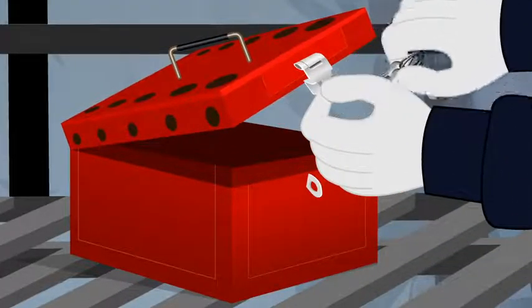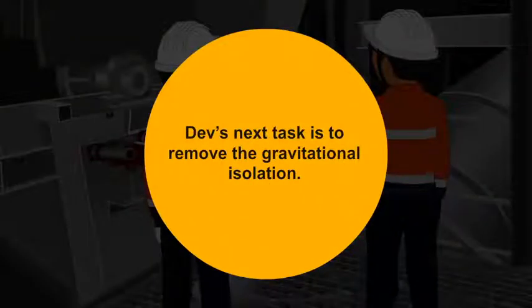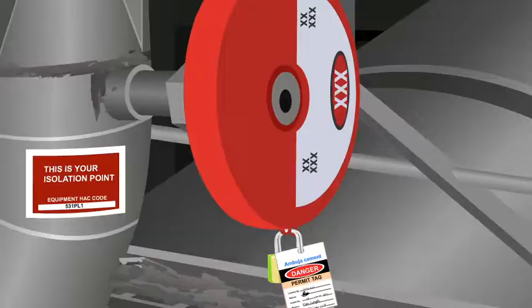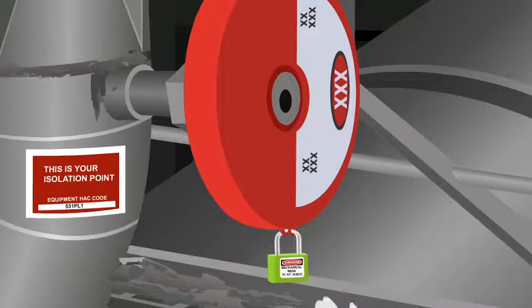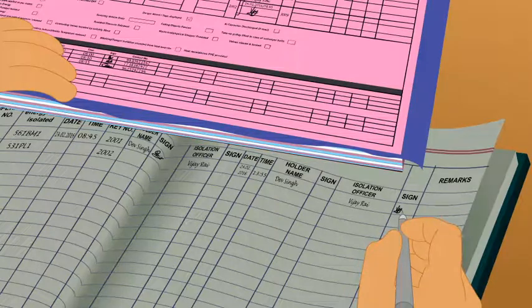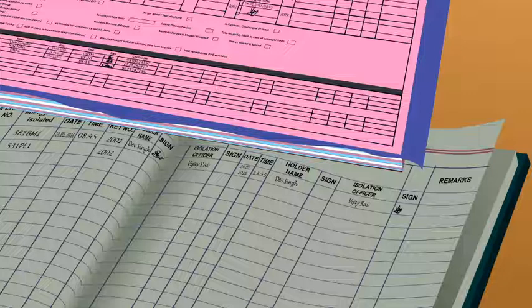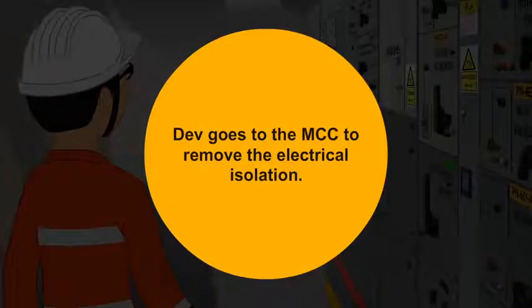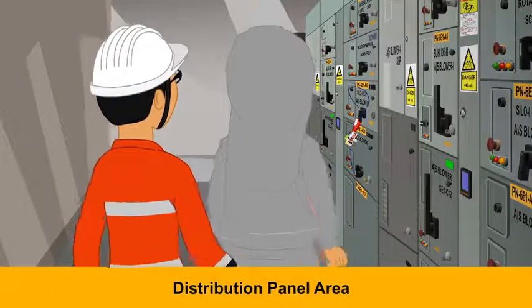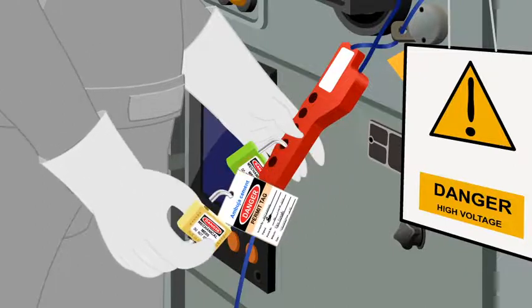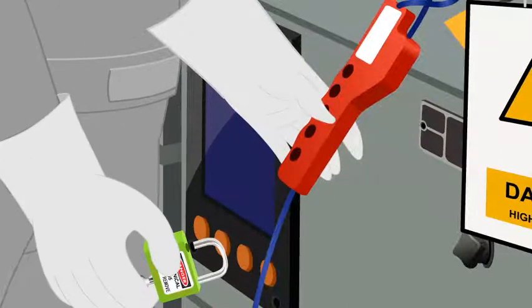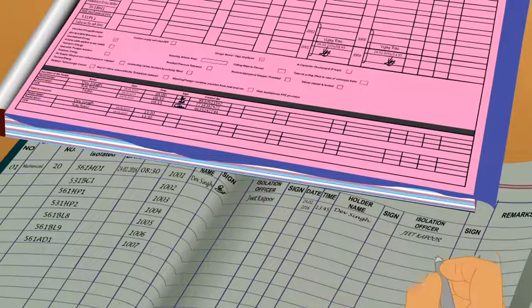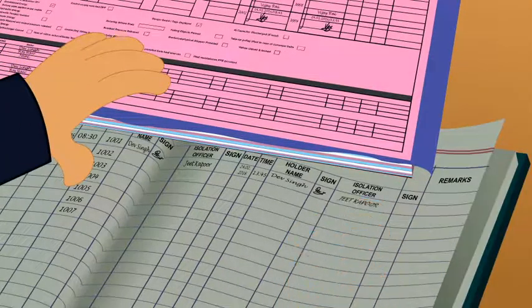Dev retrieves his keys and the permit from the lockout box. He removes his department lock first, then VJ removes his lock and signs on the isolation logbook. Dev also signs. VJ then signs on the permit. Dev and Jeet go to the distribution panel area, where Jeet removes Dev's yellow lock and then his own green lock for all the electrical energies he isolated. Jeet enters details in the isolation logbook confirming the permit is closed, Dev signs the register, and Jeet signs on the permit.